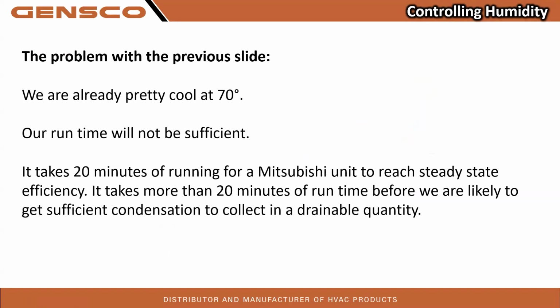I need to point out that in Mitsubishi units, it takes 20 minutes of running for a unit to reach its steady state efficiency. 20 minutes. In a unitary system, that's only 6 or 7 minutes. But for us, 20 minutes before we're at optimal coil temperatures. It takes more than 20 minutes of runtime before we are likely to even get sufficient condensation to collect in a drainable quantity. So if we run for 10 minutes and stop, guess what happens to the water that did condense on the coil? It evaporates back into the air, except we've cooled the air.